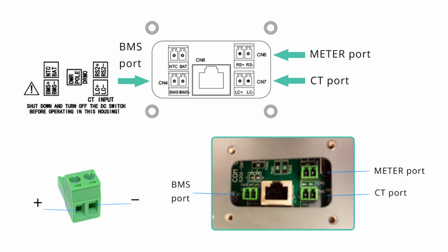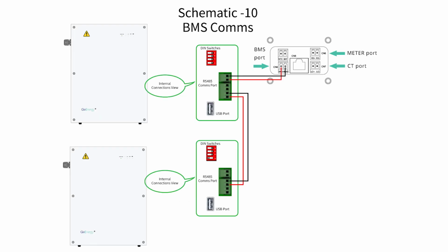Now the connections from the inverter to the battery. Using the 2-core cable supplied with the battery, connect the terminals BMS port positive and negative on the inverter to the battery connection RS485. If you're connecting more than one battery, connect them together using the 4-pin terminal connections to and from each battery.